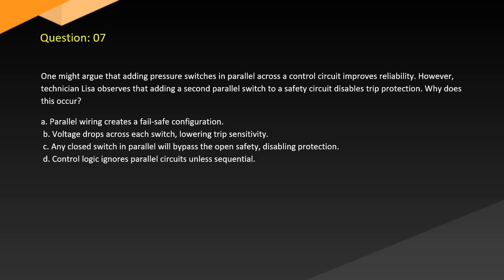Question 7. One might argue that adding pressure switches in parallel across a control circuit improves reliability. However, technician Lisa observes that adding a second parallel switch to a safety circuit disables trip protection. Why does this occur? A. Parallel wiring creates a fail-safe configuration. B. Voltage drops across each switch, lowering trip sensitivity. C. Any closed switch in parallel will bypass the open safety, disabling protection. D. Control logic ignores parallel circuits unless sequential.